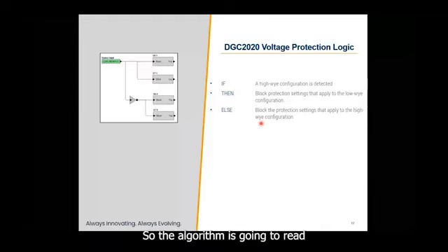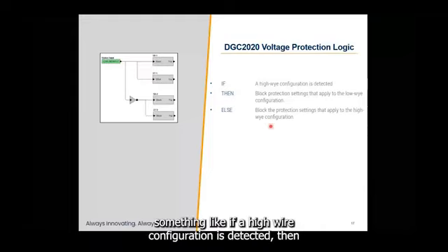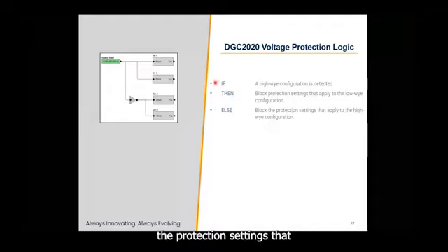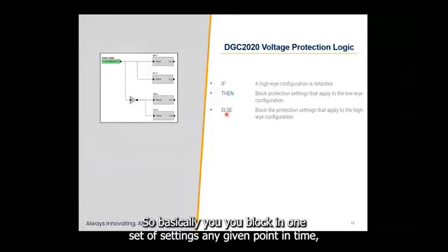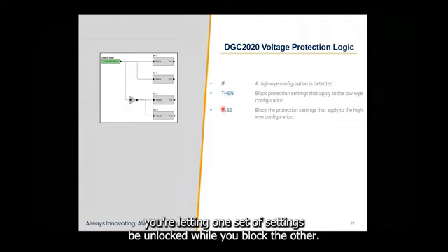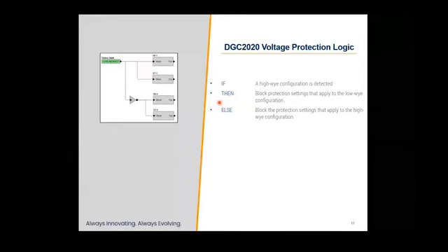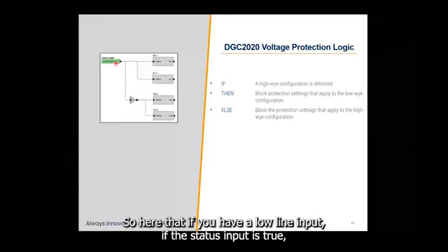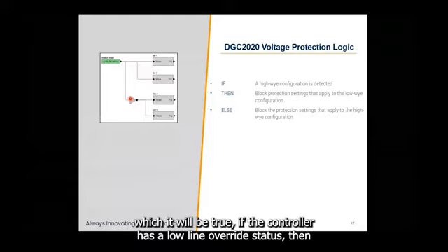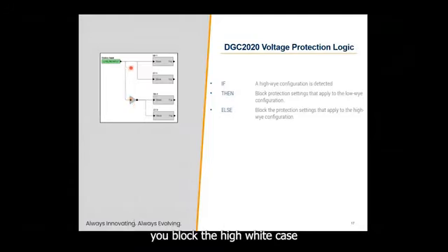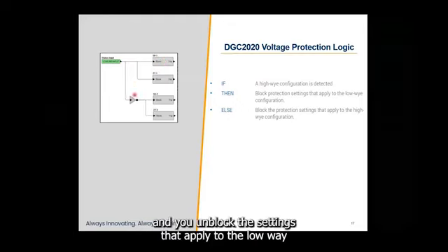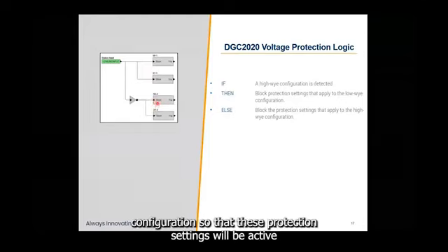And here's your logic scheme. So the algorithm is going to read something like, if a high-wye configuration is detected, then block the protection settings that apply to the low-wye configuration. Else, block the protection settings that apply to the high-wye configuration. So basically, you're blocking one set of settings at any given point in time. You're letting one set of settings be unblocked while you block the other. So here, if you have a low line input, if the status input is true, which it will be if the controller has a low line override status, then you block the high-wye case and you unblock the settings that apply to the low-wye configuration, so that these protection settings will be active and these will not be active. And then the logic just flips for the high-wye case.